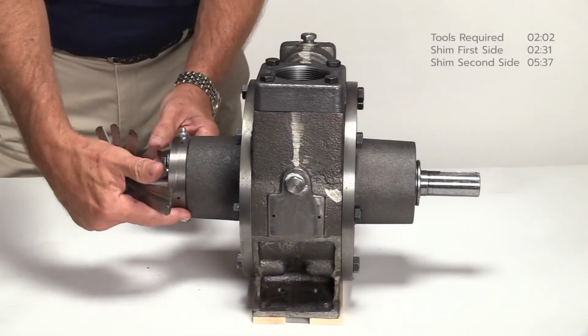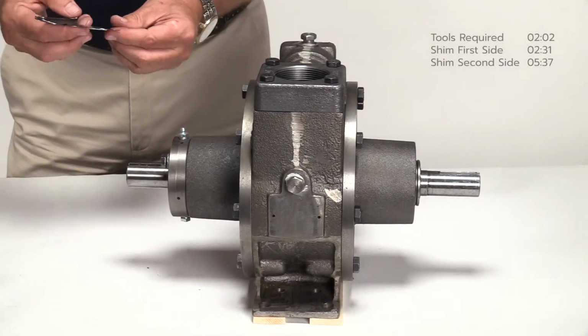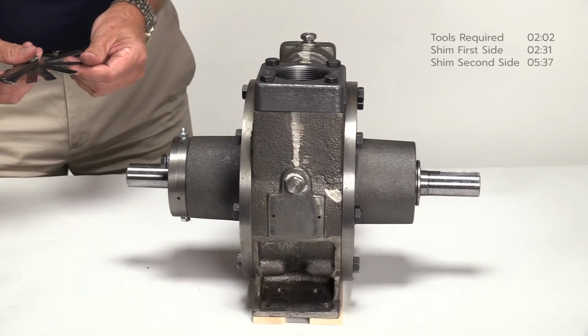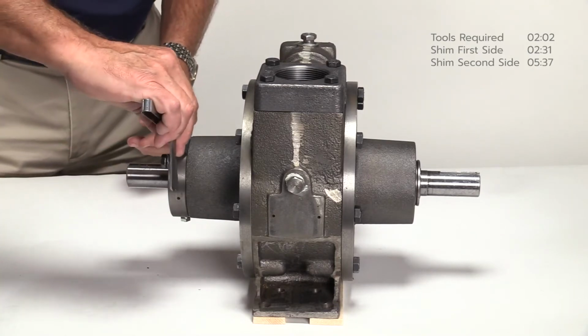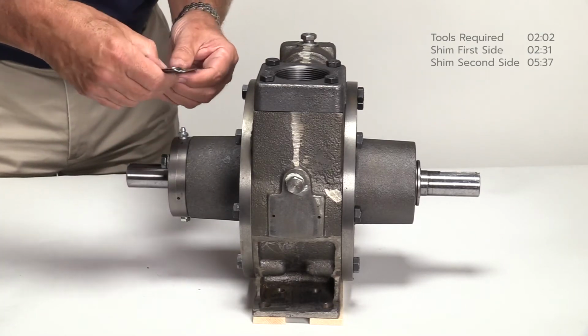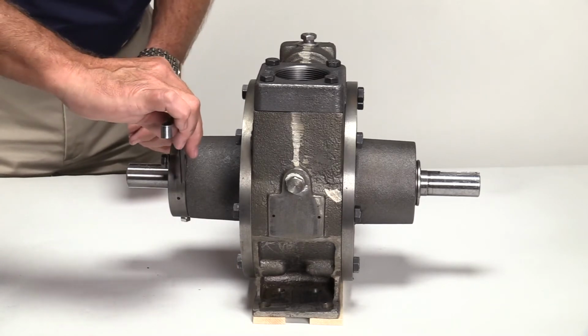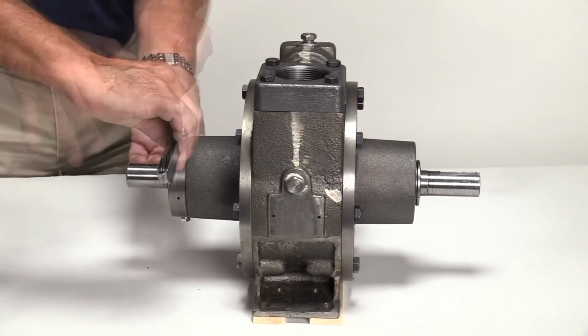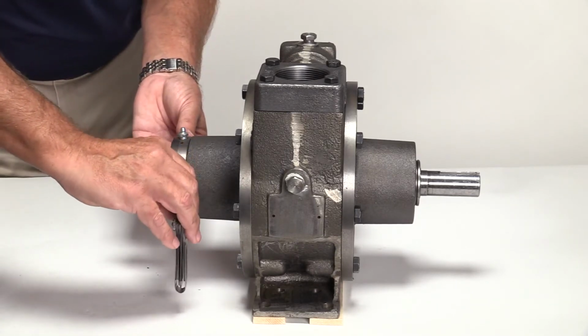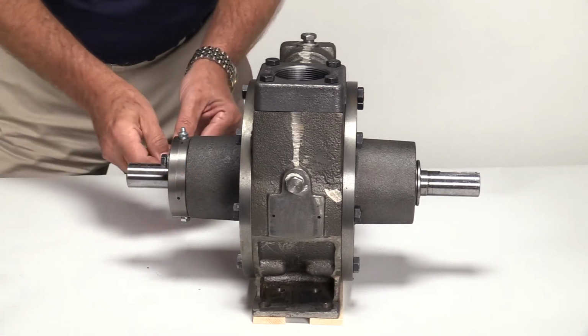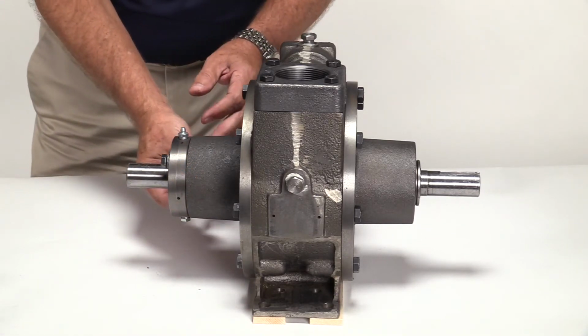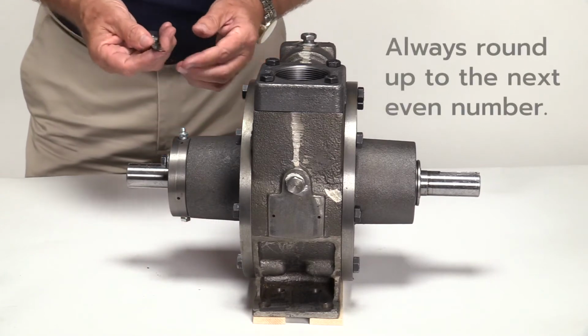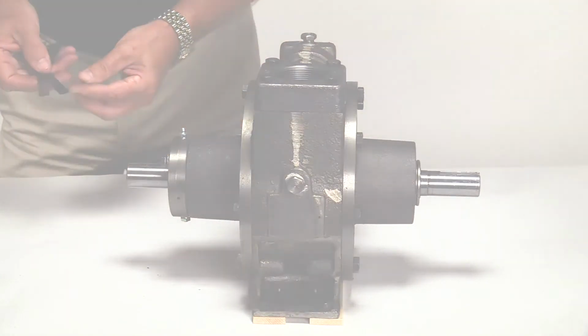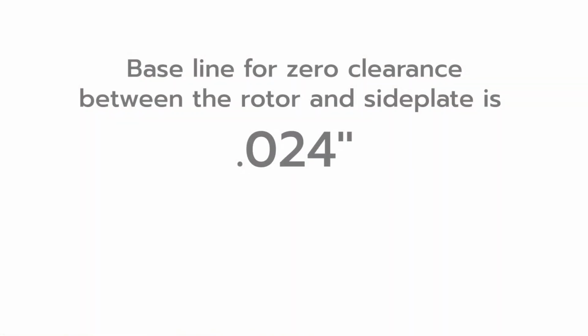Use the thickness gauge to measure the gap between the bearing cap and the pump head at multiple points as shown. This gap establishes a baseline for zero clearance. The gap should be the same at all points. If not, the bearing cap is not mounted flush with the pump head. The gap measures 23 thousandths. Always round up to the next even number. So, in this case, the baseline for zero clearance between the rotor and side plate is 24 thousandths.